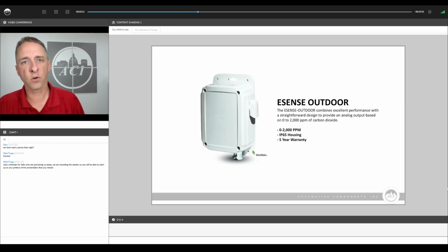The nature of the CO2 sensing element is that it has a very limited temperature range that it operates effectively in. So we created an outdoor unit that has an integral heater so that it heats the air to bring it up within the operating range of the CO2 sensor, so you can get an accurate and stable reading in an outdoor enclosure, especially in areas where it can get very cold, like here in Wisconsin. This sensor is fixed at a 0 to 2,000 parts per million range and has a full 5-year warranty like our other CO2 sensors that we've talked about.